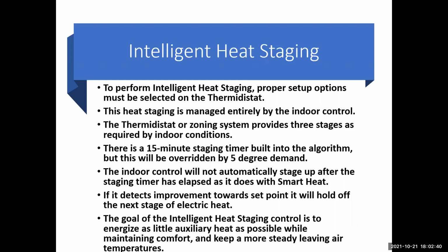Intelligent heat staging. To perform intelligent heat staging, proper setup options must be selected on the thermostat. The heat is staged and managed entirely by the indoor control board, or the indoor control, your thermostat. The thermostat or the zoning system provides 3-stage as required by indoor conditions. There's a 15-minute staging timer built into the algorithms, but this will be overridden by a 5-degree demand. So if you set it up 5 degrees higher, you can override that 15 minutes.